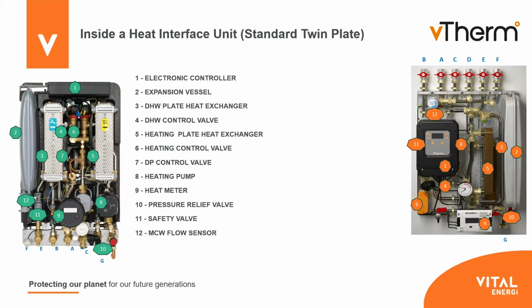And in some cases, the safety valve can also be doubled up, and that can be used also as a prepayment valve as well. So it can have a dual functionality. We've then got the mains cold water flow sensor. That's normally some form of turbine or maybe an ultrasonic sensor. And therefore, that's what triggers the heating demand, hot water demand, and therefore starts that cycle. And then you might have a temperature gauge, pressure gauge, or it could be that it's being displayed on your electronic controller. And then we've got various drain and fill valves.